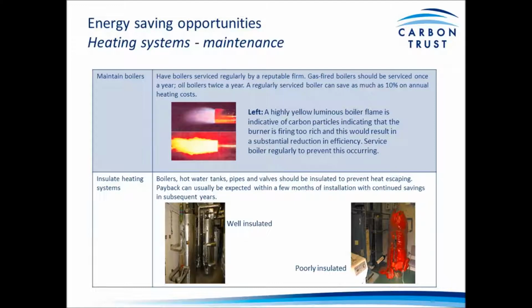And you should ensure that all valves and pipework joints are insulated, as an uninsulated valve can emit as much heat as around a metre of pipework of the same diameter. So it's something we see very commonly, just heat being wasted into boiler rooms and plant spaces, service spaces, just because insulation hasn't been upgraded. And again, this isn't something you would necessarily see as an inefficiency as a building user.